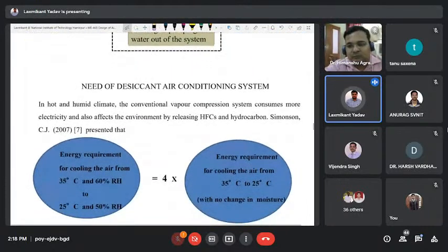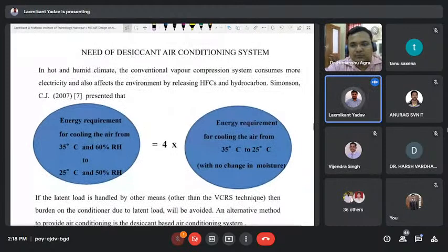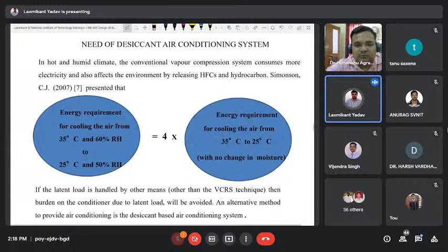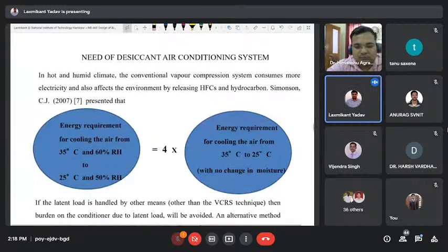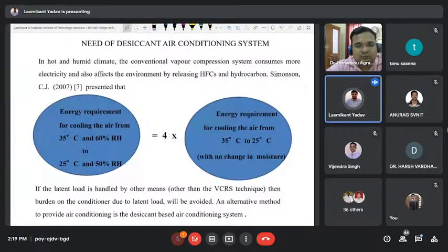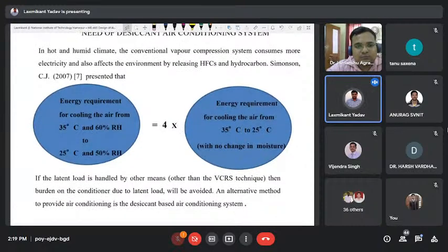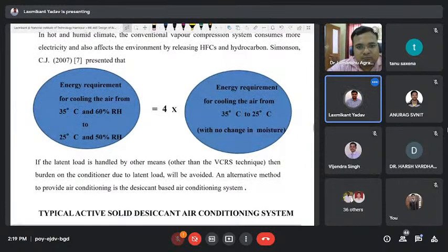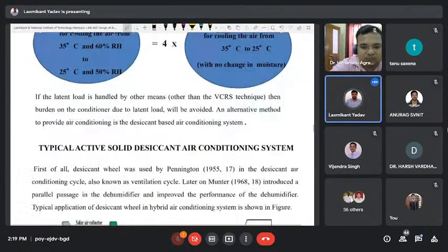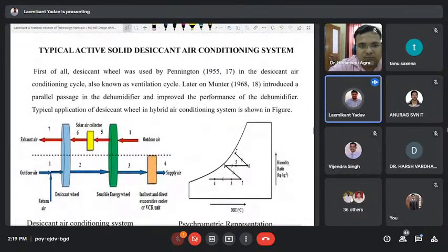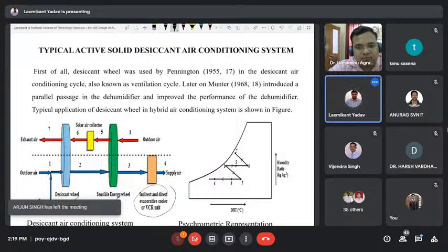So why is a desiccant system required? Because we can control the humidity separately. In the case of a conventional system, we control the sensible cooling and latent cooling simultaneously. But if we use the desiccant wheel, we can control the humidity separately and we can control the temperature separately. So separate control is quite accurate. So we can control both temperature and humidity separately with the use of a desiccant air conditioning system. So these are the typical solid desiccant air conditioning systems where we use a desiccant wheel, enthalpy wheel, and direct and indirect evaporative cooler for the air conditioning.